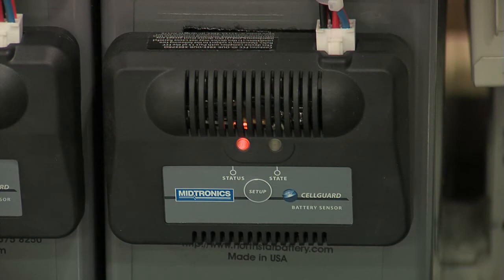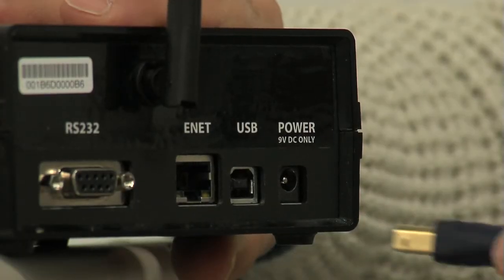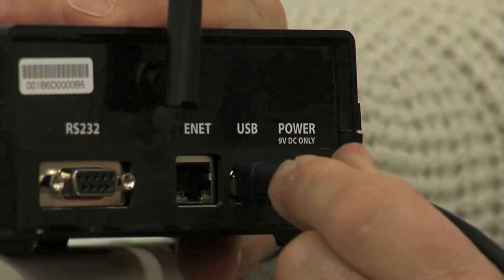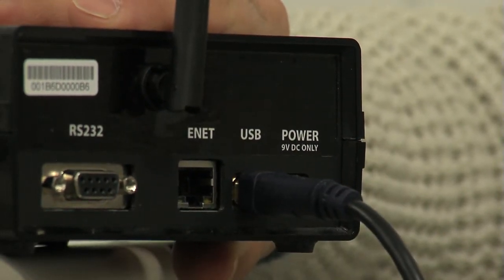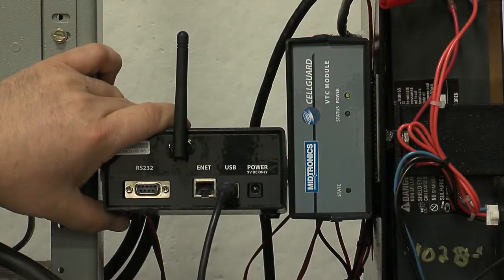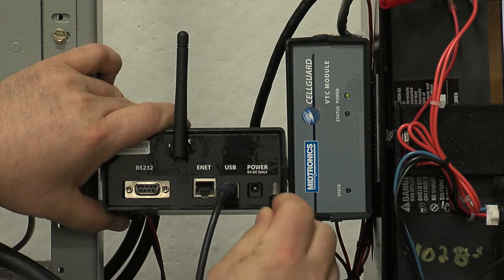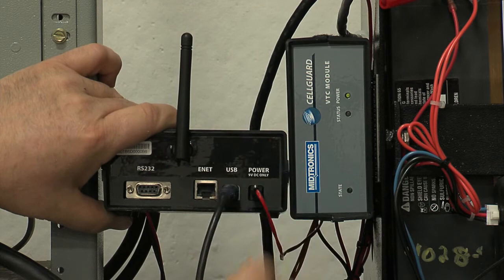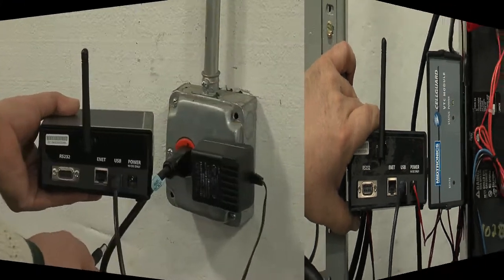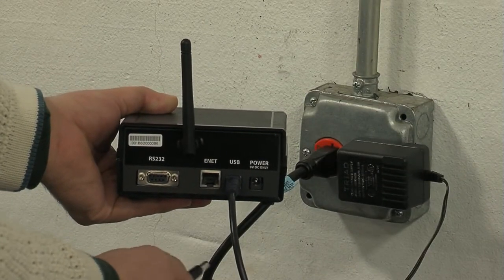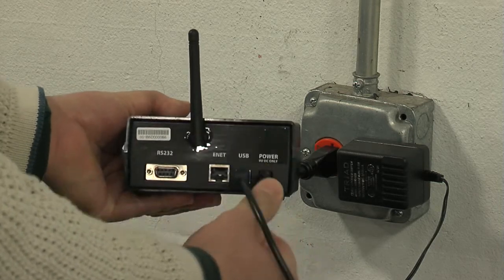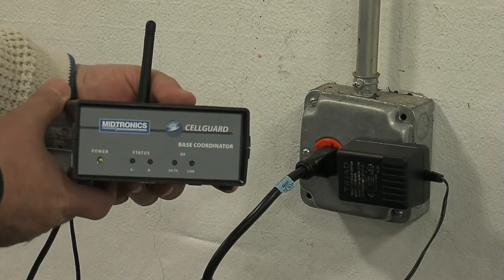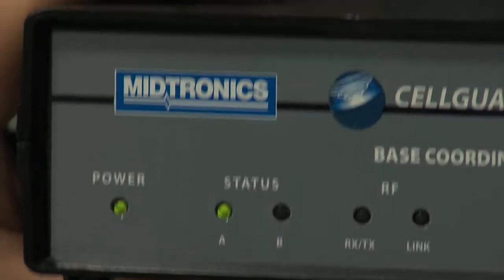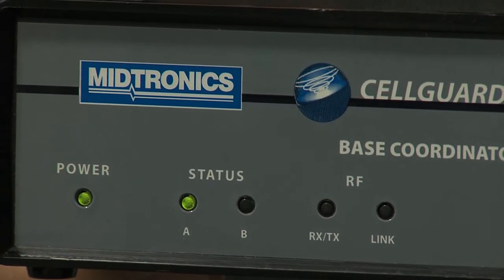We're now ready to start the Cellguard hardware commissioning process. Connect a USB cable or RS-232 cable from your PC to the Base Coordinator Unit, BCU. Next, power up the BCU by using the power cable coming from the VTC. If you do not have a VTC or do not have power from the VTC, use the BCU's external power supply. The power LED should be green, indicating the BCU is on.